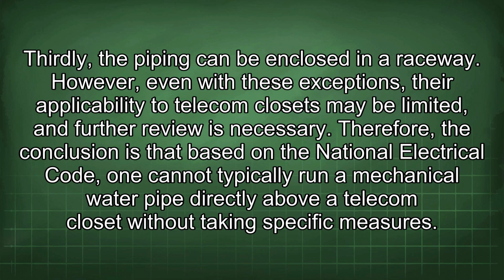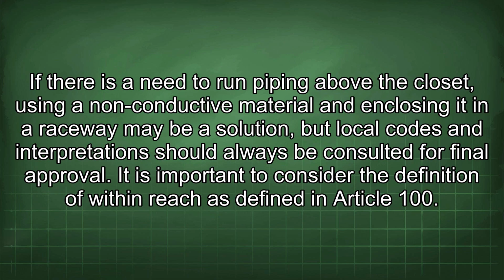Therefore, the conclusion is that based on the National Electrical Code, one cannot typically run a mechanical water pipe directly above a telecom closet without taking specific measures. If there is a need to run piping above the closet, using a non-conductive material and enclosing it in a raceway may be a solution, but local codes and interpretations should always be consulted for final approval.